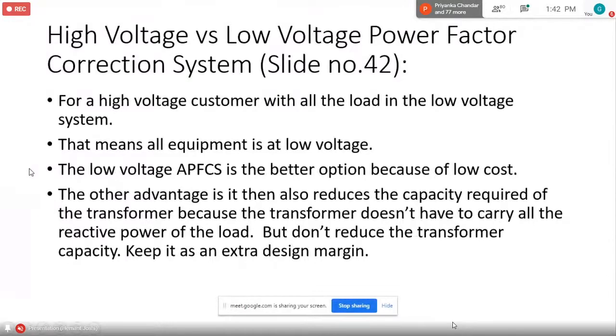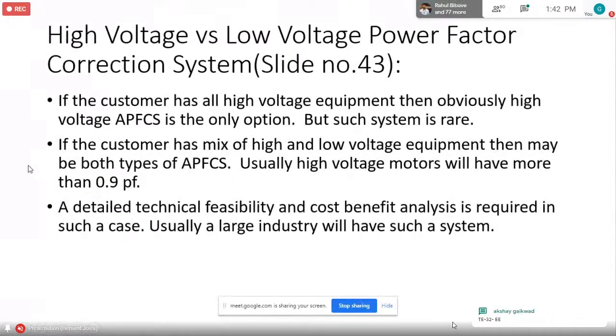And if the customer has all high voltage equipment, then obviously a high voltage correction system is the only option. But such a system is rare. If the customer has a mix of high and low voltage equipment, then maybe both types of APFC. Usually high voltage motors will have 0.9 power factor or more even. So having to put in a high voltage power factor correction system is a very, very rare situation. You will encounter that only in a very large industry, especially steel, metallurgical, mining, that kind of big industry which has huge load demand. Not otherwise. Most light industry, medium industry and commercial buildings are low voltage, so it's very rare to put in high voltage.